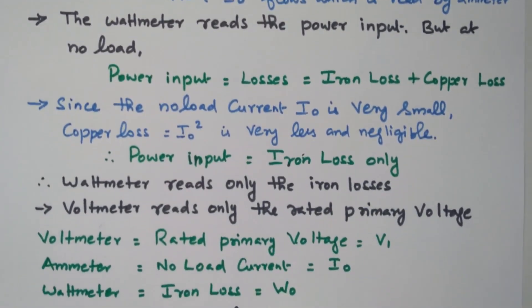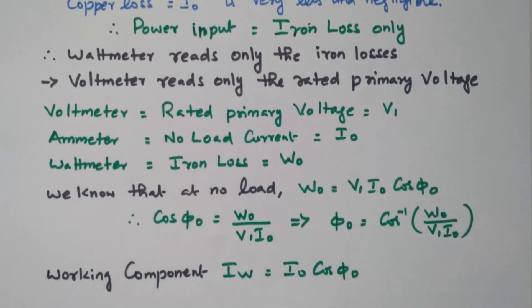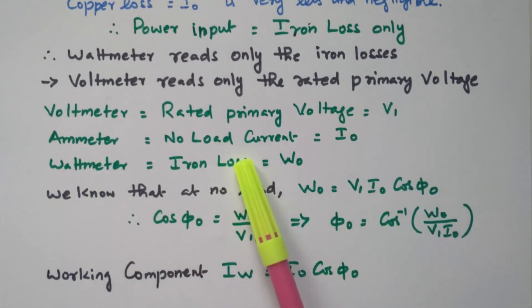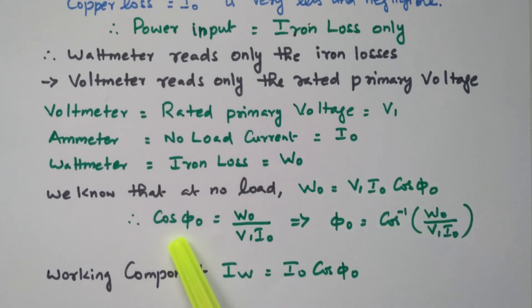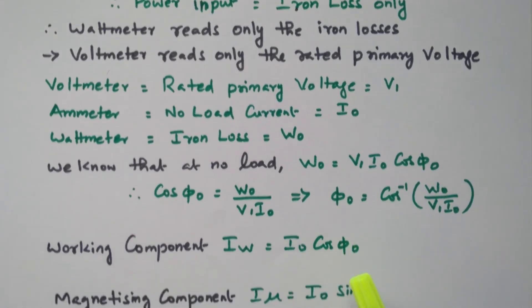From the instrument readings we can calculate R₀ and X₀. The voltmeter reads the primary rated voltage V1, the ammeter reads the no load current I₀, and the wattmeter reads the iron loss W₀. W₀ equals V1 · I₀ · cos φ₀, so cos φ₀ equals W₀ divided by V1 · I₀. The phase angle φ₀ between V1 and I₀ is then calculated as cos⁻¹(W₀ / V1 · I₀). From this we obtain the phase angle between current and voltage.